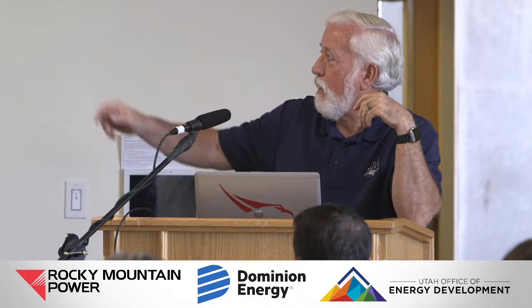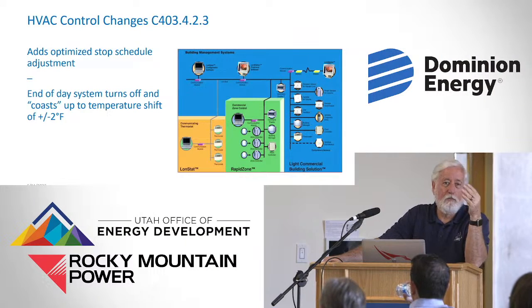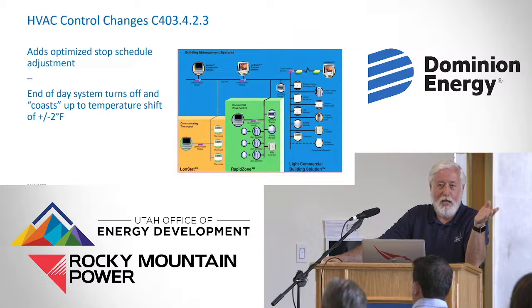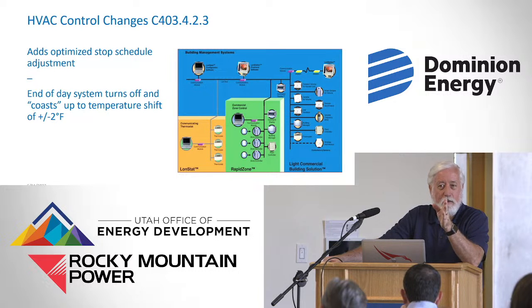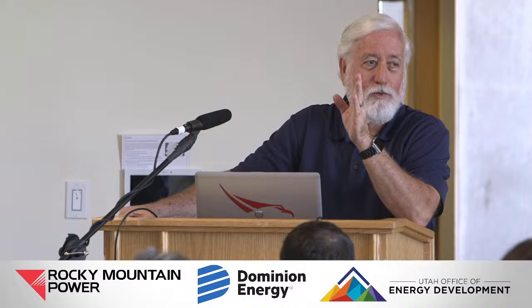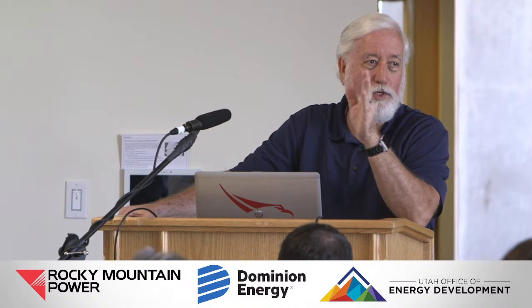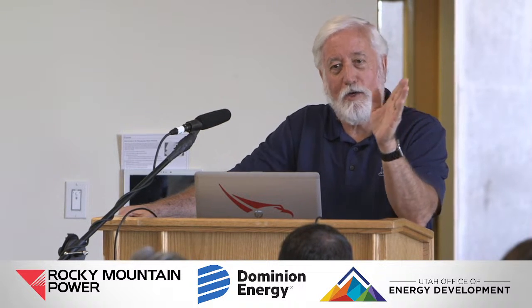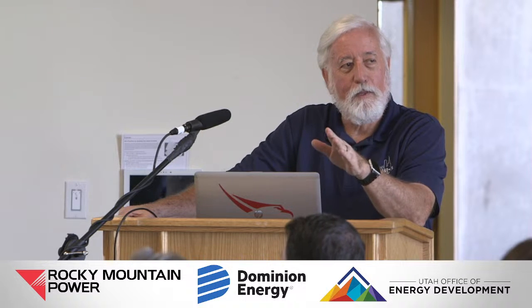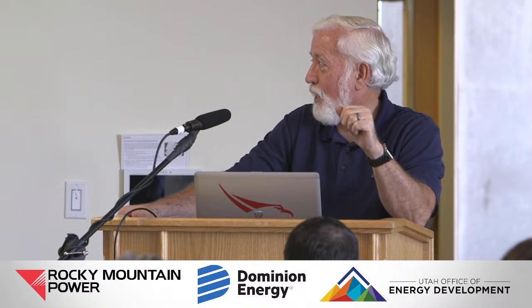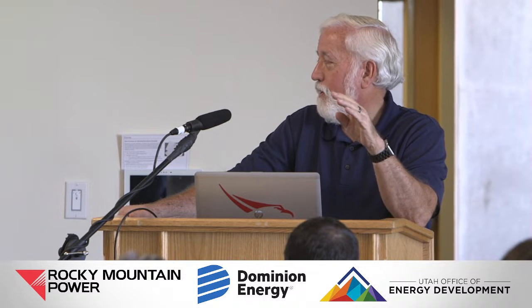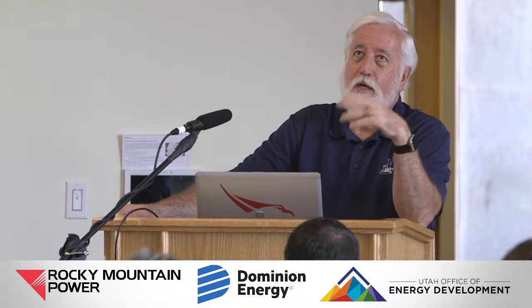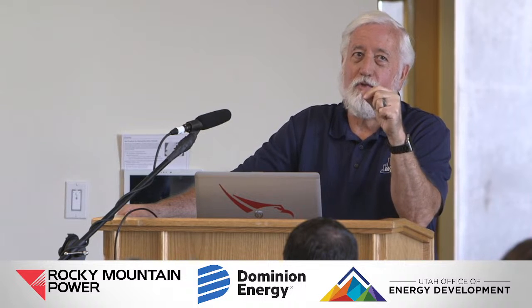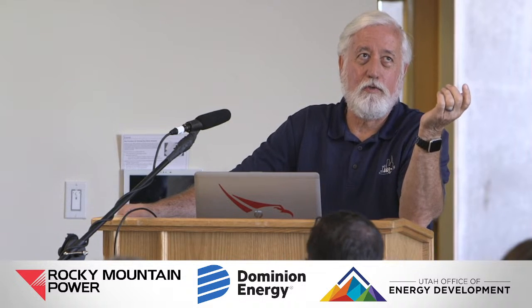Well, optimized stop scheduling looks at the building, looks at how fast it cools down or how fast it warms up, depending on the season. And it looks at, well, it's 5 o'clock, but we know that no one's going to whine if we're 2 degrees colder or 2 degrees hotter at 5 o'clock. So we're going to shut it off a little bit earlier so we kind of coast into our setback or setup. It's an additional feature. HVAC controls for a number of years have had what we call adaptive intelligent controls.